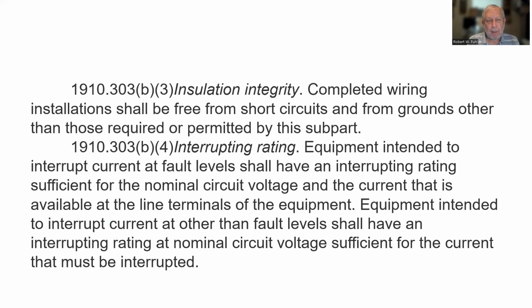Insulation integrity. Completed wiring installations shall be free from short circuits and from grounds other than those required or permitted by this subpart. Interrupting rating. Equipment intended to interrupt current at fault levels shall have an interrupting rating sufficient for the nominal circuit voltage and the current that is available at the line terminals of the equipment. Equipment intended to interrupt current at other than fault levels shall have an interrupting rating at nominal circuit voltage sufficient for the current that must be interrupted.